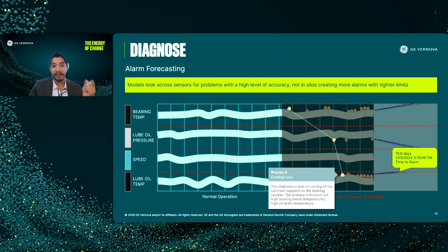So we have a diagnosis. The next question you may have: how long do I have? What we're showing here illustrates SmartSignal's time-to-action forecasting capabilities. SmartSignal forecasts when you might cross that asset's limits, similar to your DCS alarm set points. In this specific bearing example, SmartSignal identifies the asset's going to reach a critical alarm in 10.8 days.